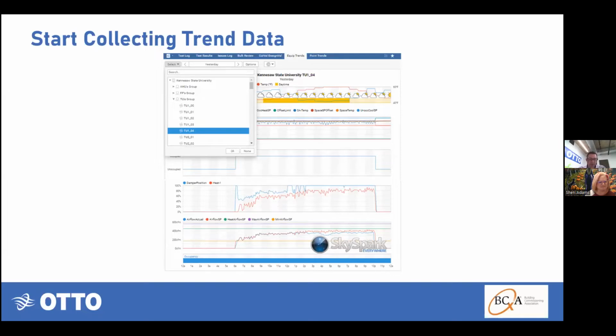They can get rather complicated. We have building blocks like everybody would for test scripts, and we work off those, but everything is adjustable and sometimes needs to be adjusted for a particular project. There might be unusual modes—like a CO2 sequence for a terminal unit box to open up all the way, or an occupancy sensor in the space that allows set points to be relaxed. All those things can be integrated now with our automated script. But there are normally things on a typical functional test script that include physical stuff, or point-to-point checks that should have been done separately. Whatever it is, every script I've seen from a commissioning provider has some physical element OTTO just can't replicate. So we have to be realistic: this is a supplement that takes away a lot of your tedious, repetitive work and gives you visibility you've never had before, but you still have core responsibilities we cannot displace.